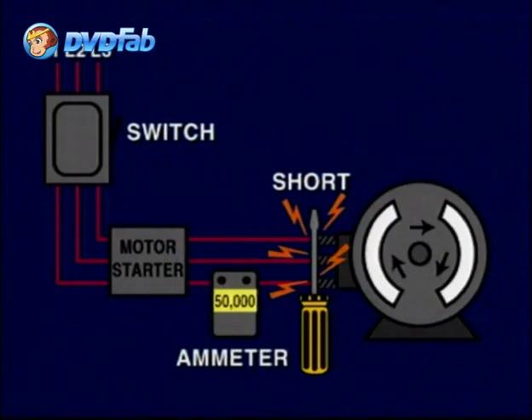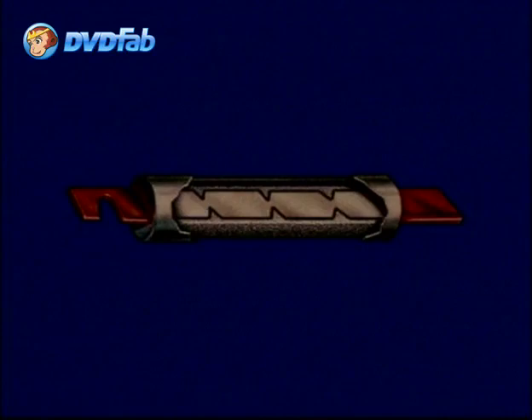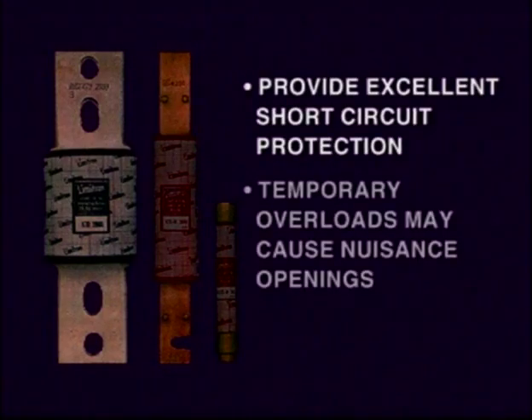The single-element fuse, when exposed to these short-circuit conditions, will have all of its links melt simultaneously. The short-circuit current is cut off in less than half a cycle, or about 8.3 thousandths of a second, long before the short-circuit current can reach its full value. Single-element fuses provide excellent short-circuit protection. However, temporary and harmless overloads, like those created by motors, may cause nuisance openings unless the fuses are oversized.